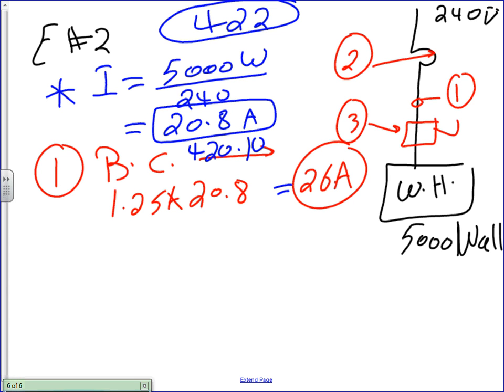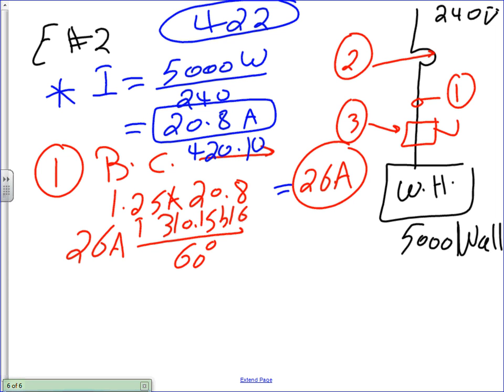Cool? 26 amps. Now, the next step is, you take 26 amps and take this to Table 310.15(B)(16), guys. Under which column and why? Is this a motor? No. So what's your default? 100 amps or less? 60. More than 100? 75. So go to 100 or less. What's under the 60-degree column? So we're going to go to the 60-degree column. What's the size? Number 10? Can I have a second? Number 10. So how many conductors though?